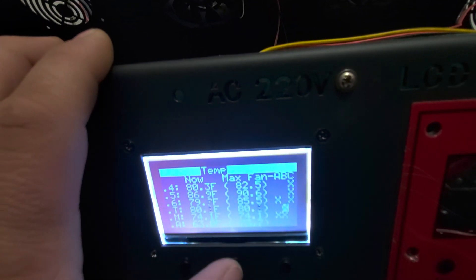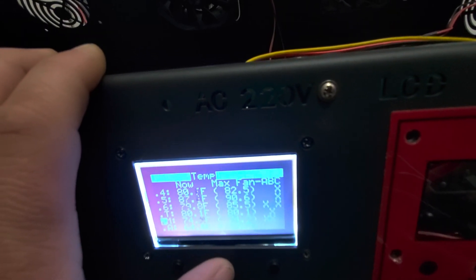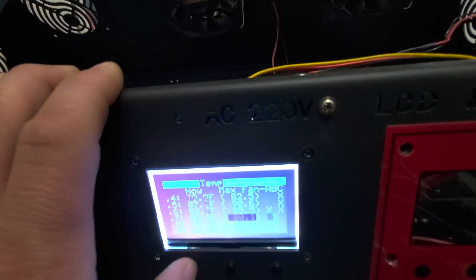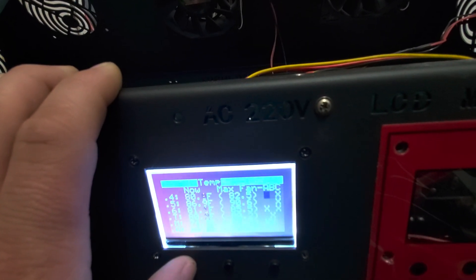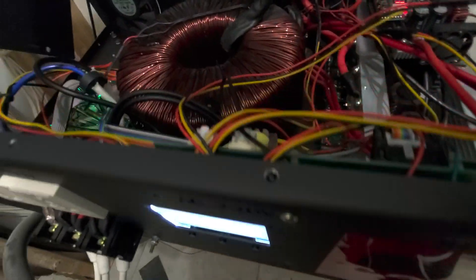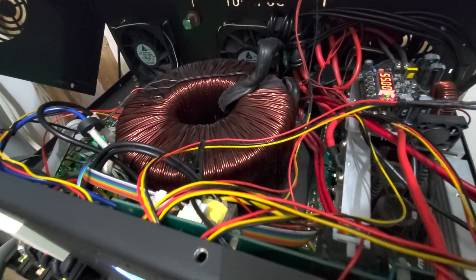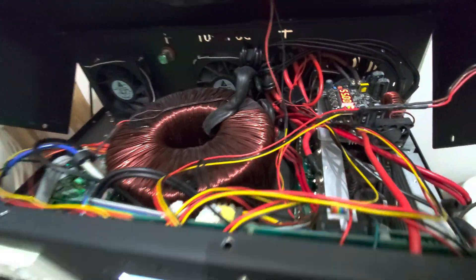Yeah, it's a lot to scroll through. There we go, there's our ambient temperature, 63 degrees in this room. The most it's ever seen is 73, which I'm not understanding why because it's definitely not been 73 in this room. It might be a fluke of some kind. But yeah, there's the main board temperature, there's the transformer temperature, and then all of these sensors here, all the ones that I have actually added to the inverter. I'm occupying every single space on this board and you can see all those wires are coming out of there.